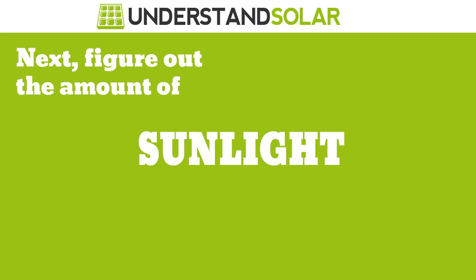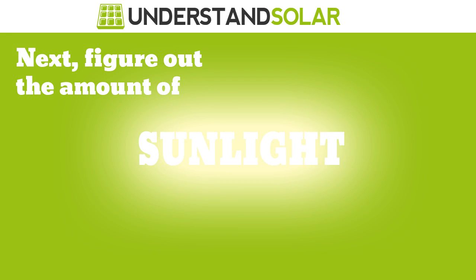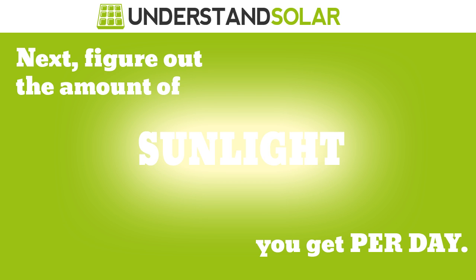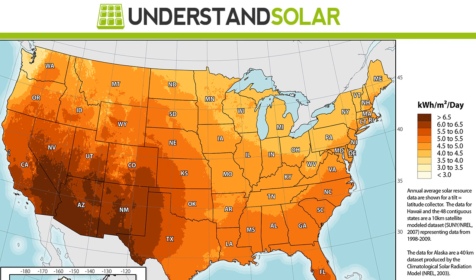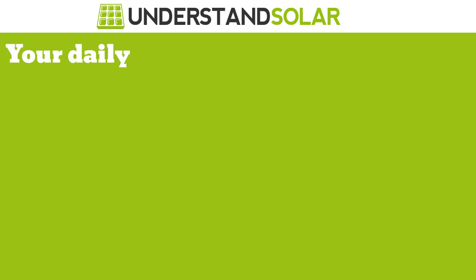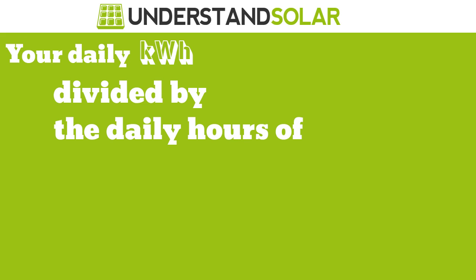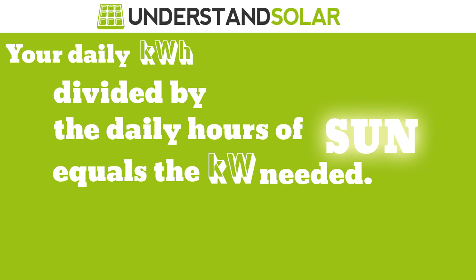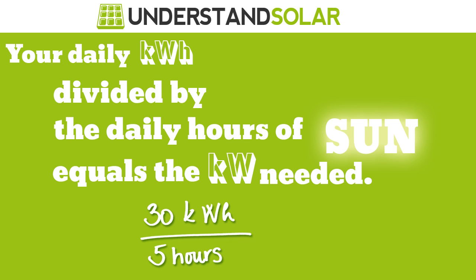Next, figure out the average amount of sunlight you get per day. The US ranges from about 4 to 6 hours of sunlight per day. Find your location on this map and the corresponding number in the right column. Let's estimate you get about 5 hours per day to generate that 30 kilowatt hours you use. So the kilowatt hours divided by the hours of sun equals the kilowatts needed.